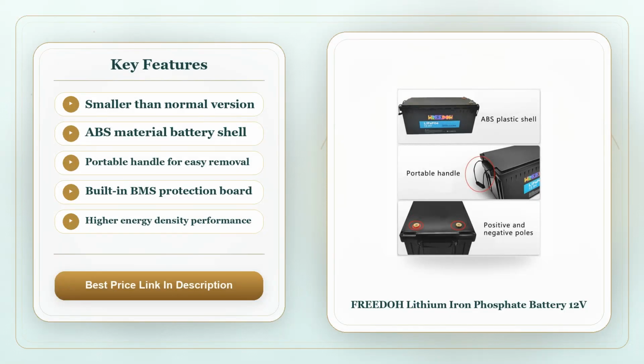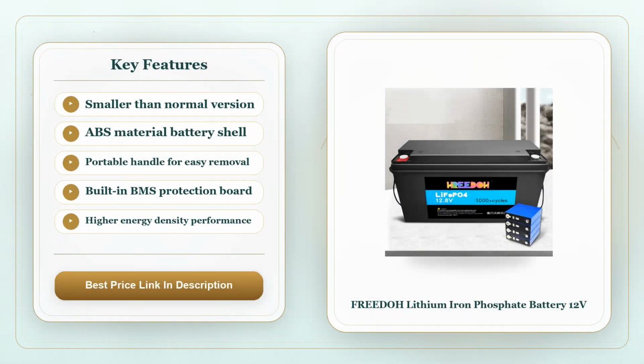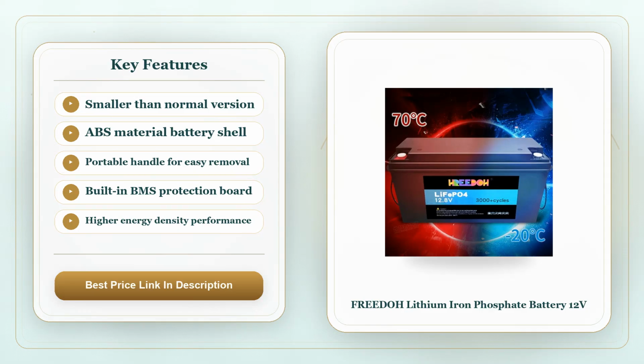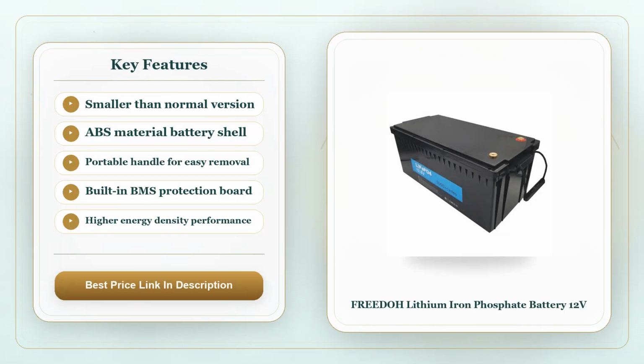However, when you factor in the longer cycle life, LiFePO4 typically lasts 2,000 cycles versus 500 to 800 for AGM, the break-even point often comes within 3 to 4 years of regular use. If you're the type of traveler who hits the road every weekend, that math starts to look favorable quickly.